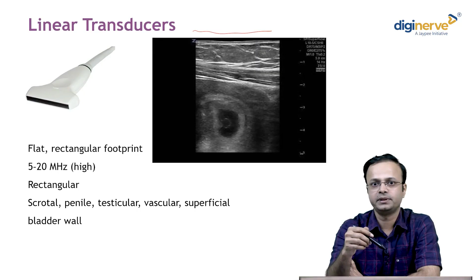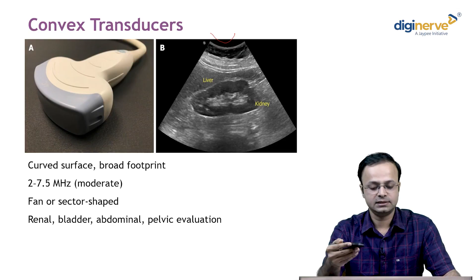We cannot assess the deeper structures because, as we already know, as the frequency increases, the depth of penetration decreases, though the resolution improves. This is a convex transducer. Here you can see that the footprint is convex. This is the transducer which we use most commonly in urology and any abdominal examination. The frequency ranges from 2.2 to 7.5 megahertz, and it is used for kidneys, bladder, and any intestinal pathology evaluation.